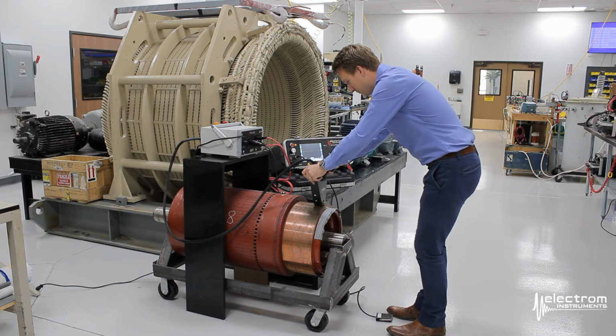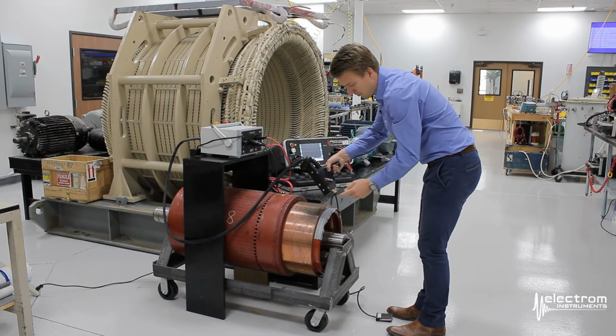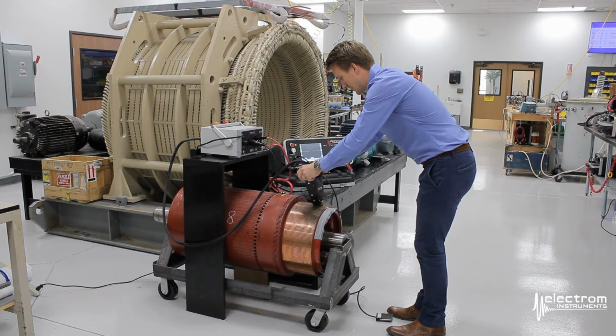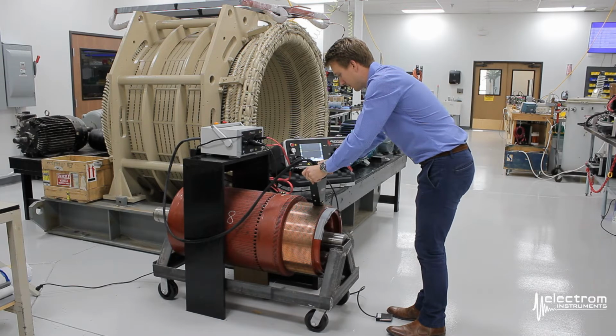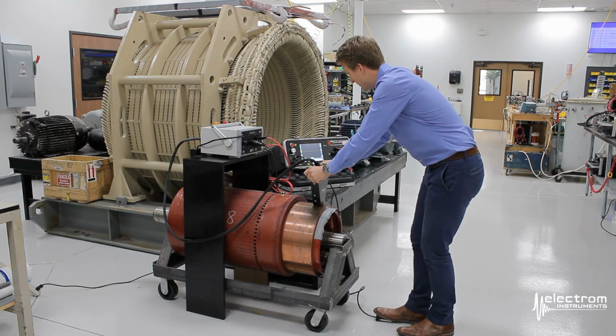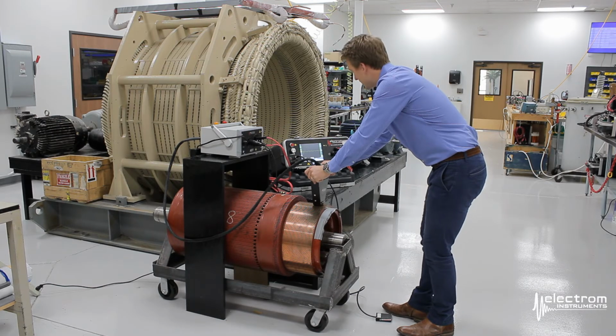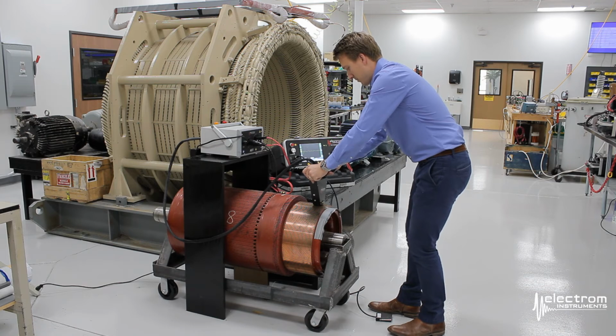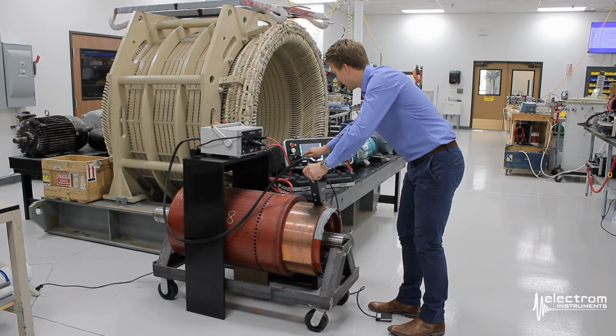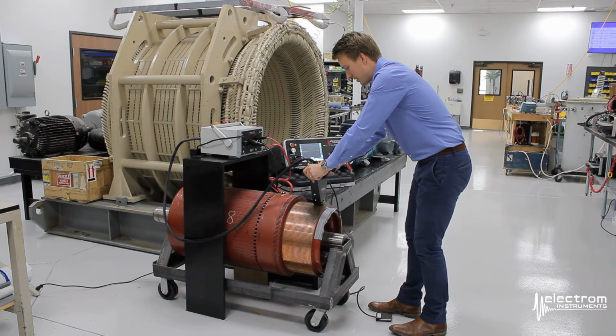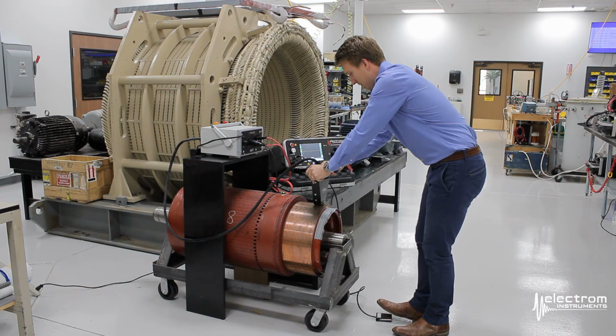So find a comfortable position, make sure that the probe tips are touching the adjacent bars, and step on the foot pedal. It'll take a few seconds for the first test to be completed, as it has to set the time base and voltage scale. When it's done, we can release the foot pedal, move 1 bar over, and then click the next coil button. So now we're in multi-coil test mode. Next step will be to press the foot pedal again.